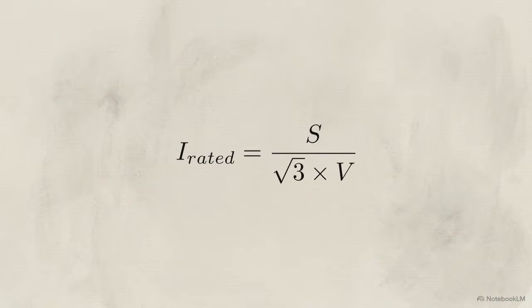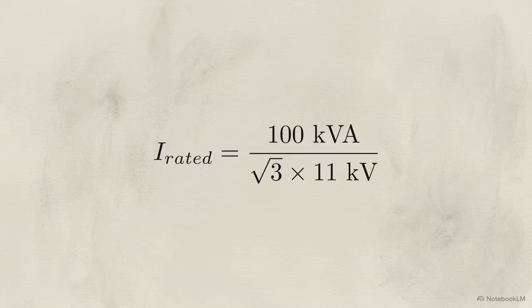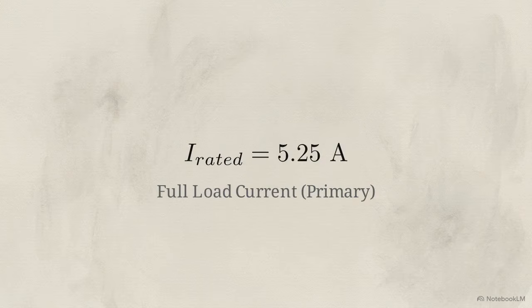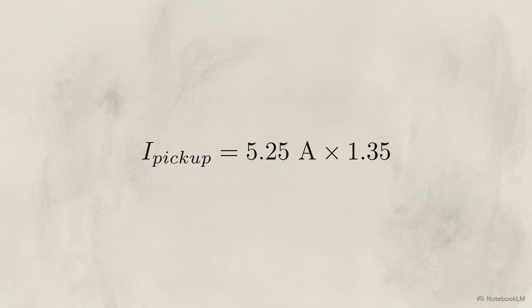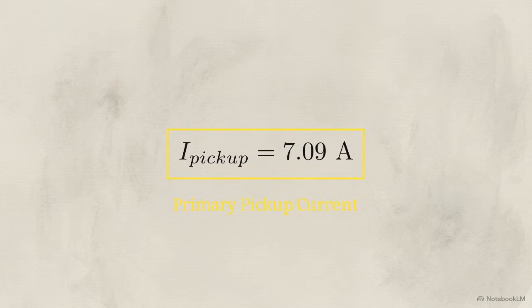You divide the rated power by the square root of 3 times its voltage. For a 100 kVA transformer at 11 kilovolts, the full load current is 5.25 amps. Next, engineers factor in a safety margin to prevent nuisance tripping during harmless inrush currents. Multiplying the 5.25 amps by a 135% safety margin gives us a primary pickup current threshold of 7.09 amps.